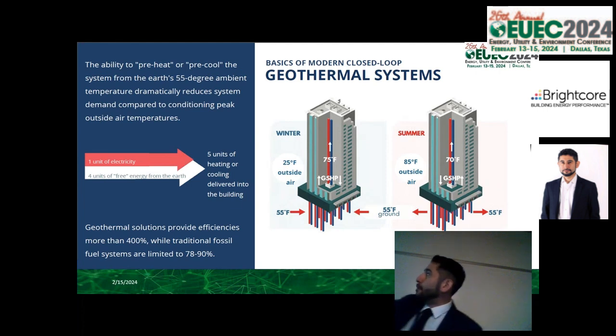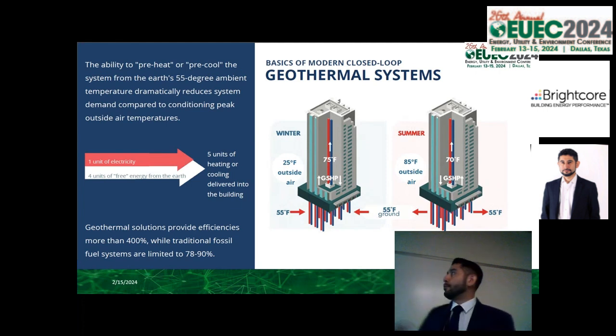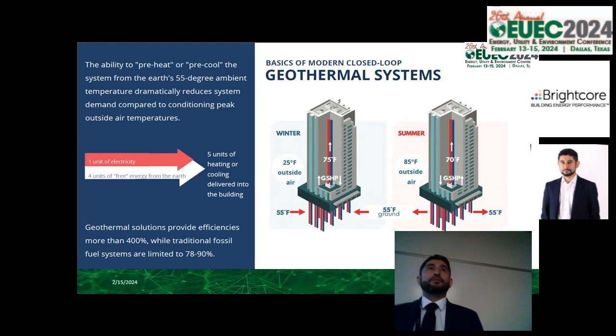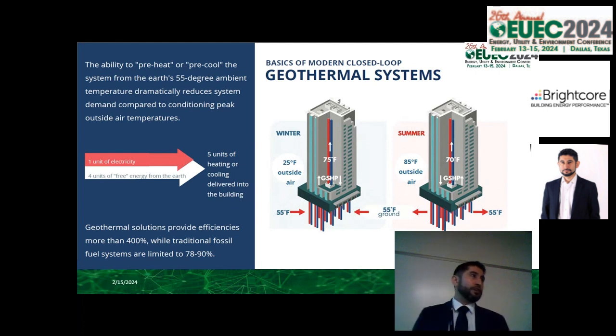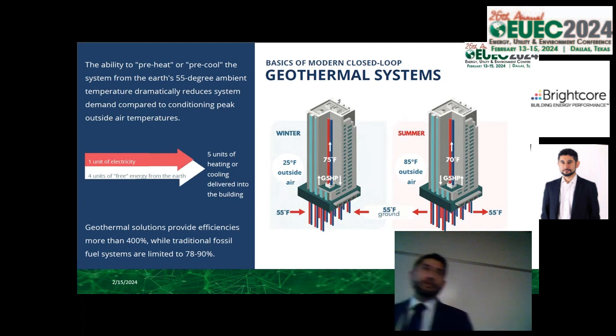would bring temperatures down to about 25. But that bedrock, at the Manhattan Schist for example, is about 55 Fahrenheit, pretty consistent. What you can do is leverage that so that you're not trying to bring 25F up to 55 or to 75 - you're bringing 55F up to 75, and that's how we're using water, which is a great exchanger fluid to pull heat or dissipate heat depending on what you need. Just like the back of your fridge is a heater and inside the fridge it's a cooler.